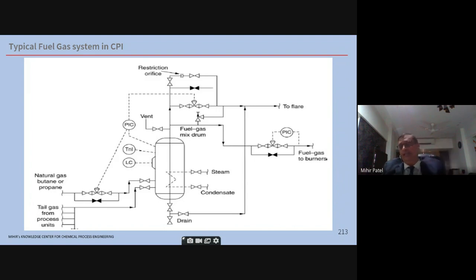So that's why a fuel gas system always has a KOD. There is a knockout drum kept at the upstream. From the outlet of this heater, the fuel gas line is always kept heat traced. Normally you use electric heat tracing to keep it at around 40-45 degrees centigrade, so that it goes in vapor stream, even in winter conditions, to the burners. And this is basically a typical fuel gas drum.